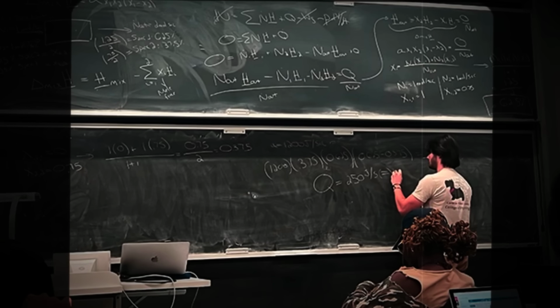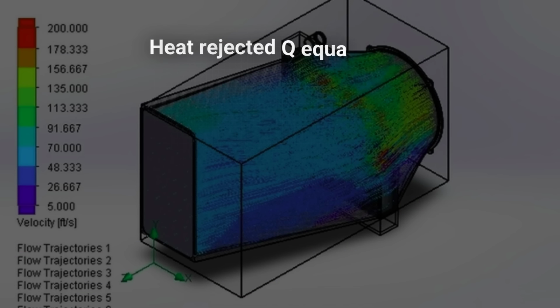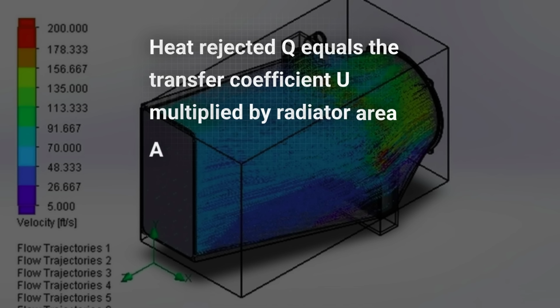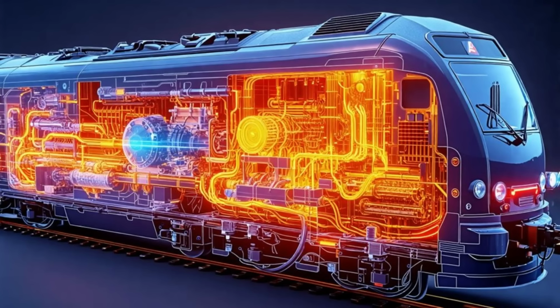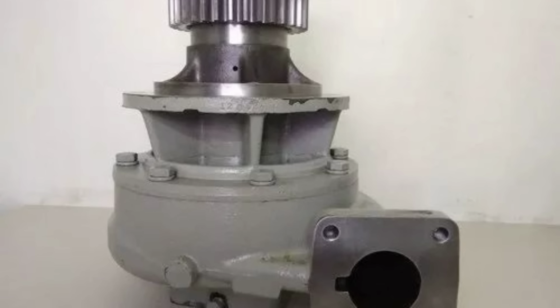The physics is simple, but relentless. The heat rejected, Q, equals the heat transfer coefficient, U, times the radiator area, A, times the temperature difference between coolant and outside air. The pump can only push so much water, and the temperature cannot go past the EPA's ceiling. That leaves only one real lever for engineers: surface area.